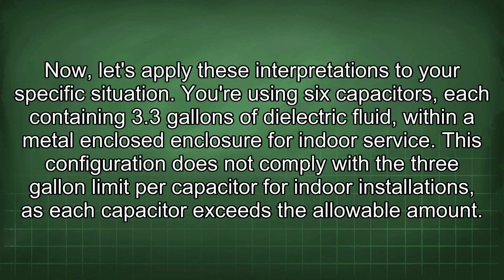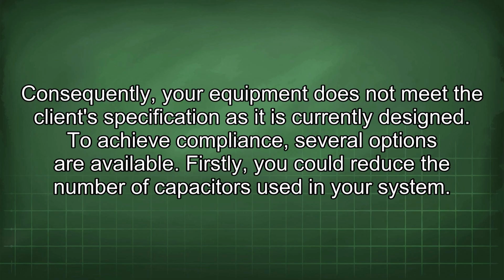Now let's apply these interpretations to your specific situation. You're using 6 capacitors, each containing 3.3 gallons of dielectric fluid within a metal enclosed enclosure for indoor service. This configuration does not comply with the 3-gallon limit per capacitor for indoor installations, as each capacitor exceeds the allowable amount. Consequently, your equipment does not meet the client specification as it is currently designed.